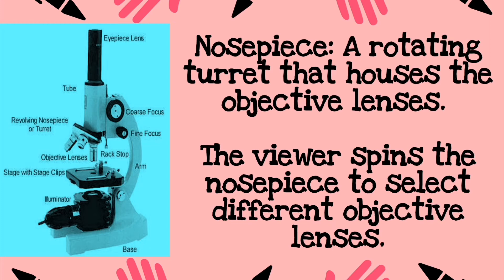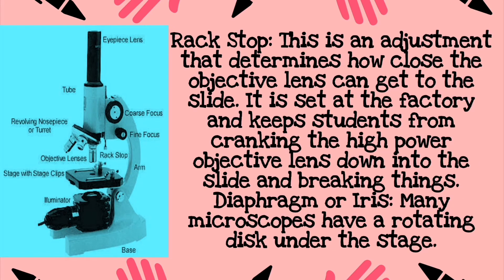Next is the nosepiece, a rotating turret that houses the objective lenses. The viewer spins the nosepiece to select different objective lenses. The rack stop is an adjustment that determines how close the objective lens can get to the slide. It is set at the factory and keeps students from cranking the high-power objective lens down into the slide and breaking things.